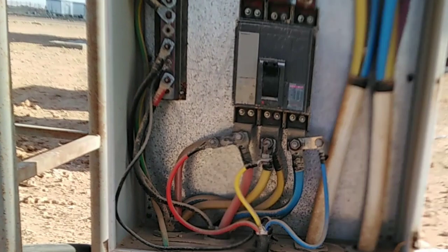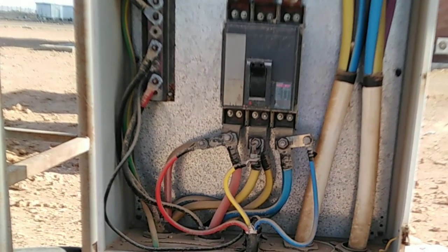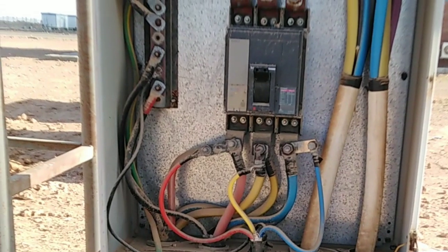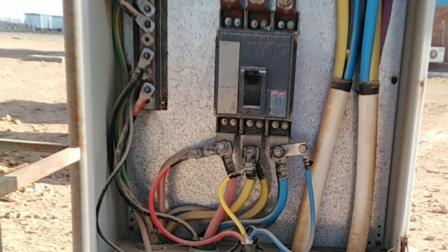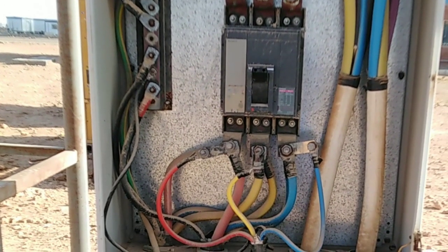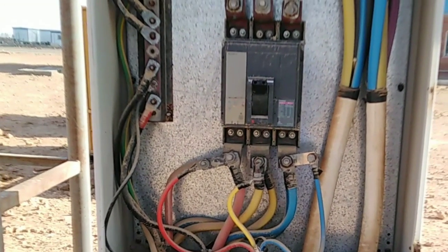An electrical error in this panel is that it has no IP protection. This means dust and water can enter the panel all the time. In heavy rain places, water can cause a short circuit. Dust can also cause a short circuit between phases if it gets wet.